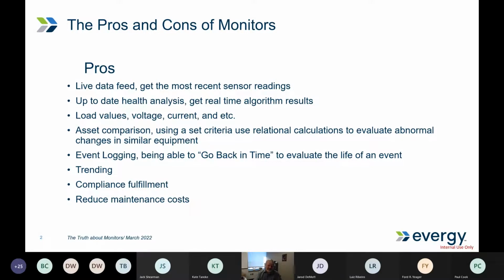But there's asset comparison, setting criteria, a relational database between this asset and that asset, covering age, manufacturer, model, style, load duty, whatever the case is. You can gather and yield a lot of information about your assets, and run algorithms that tell you if an asset is starting to age early. You can also work it out to do condition-based maintenance on that asset in a timely manner instead of waiting for that one periodic check.